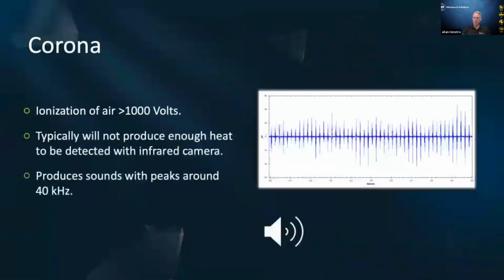So ionization, corona discharge, the ionization of air really only occurs above 1,000 volts. So if we're working with lower than 1,000 volts, there's not going to be any corona to hear anyways. And typically, corona doesn't produce enough heat to be detected with an infrared camera. So if you're only relying on thermography as a condition monitoring technology for corona, well, you can forget it. You're not gonna see that heat. But corona does produce sounds with peaks in around 40 kilohertz, and those sounds, if you have your speakers turned up, you would have heard that. That's a typical corona sound that we would hear.